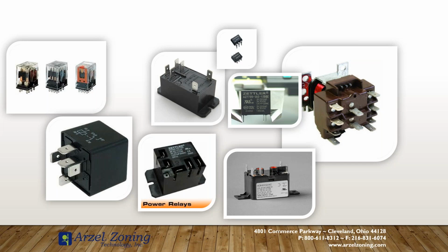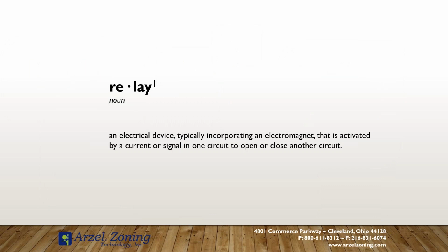The brown one there on the right side, it's not quite as popular today, but a fan center relay for a boiler system or a really old furnace that didn't have the control boards that we have today. It was a relay that plugged into the fan center socket, and that's what gave us our control of the HVAC equipment. So relays are in every part of our industry, and they really haven't changed as far as operation goes. They've just changed in appearance. But a relay is an electrical device that incorporates an electromagnet activating a switching signal that allows the path of electricity to flow. So it provides isolation, it provides control.